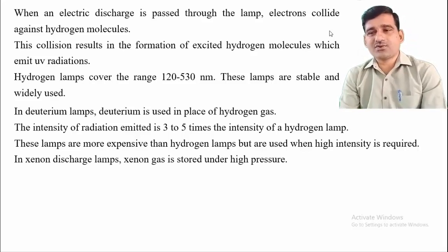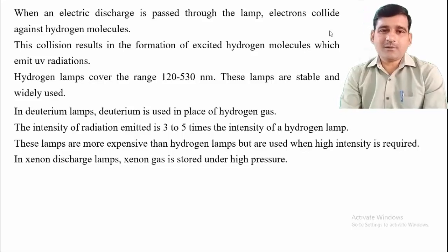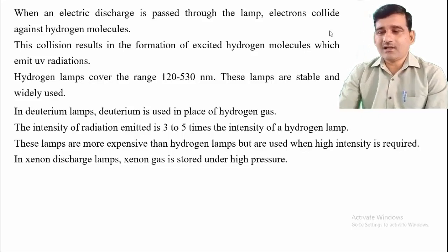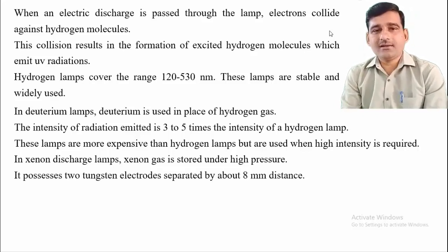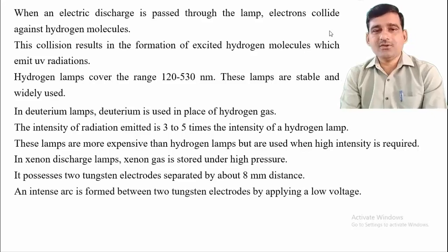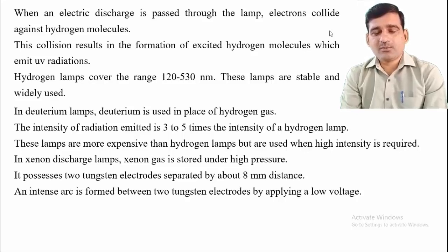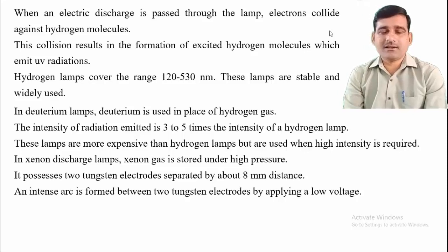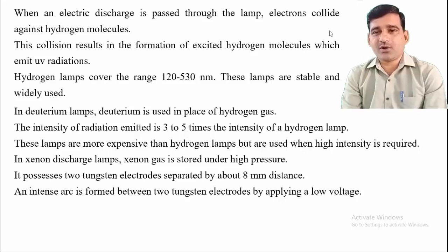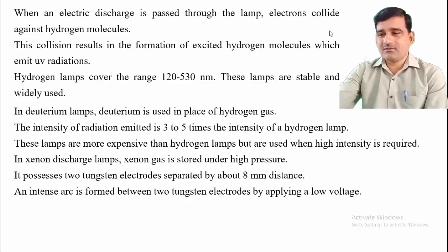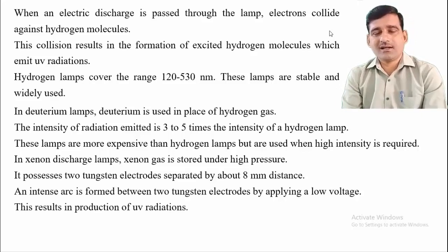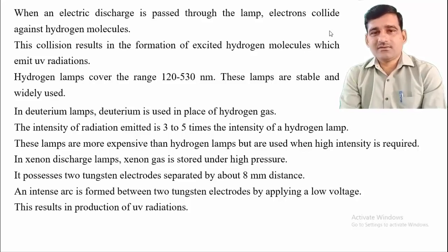In a xenon discharge lamp, xenon gas is stored under high pressure. Collision of electrons with xenon gas causes excitation, producing light in the ultraviolet region. The lamp has two tungsten electrodes separated by 8 mm distance inside an evacuated glass bulb. An intense arc is formed between the two tungsten electrodes by applying low voltage, resulting in the production of ultraviolet radiation.